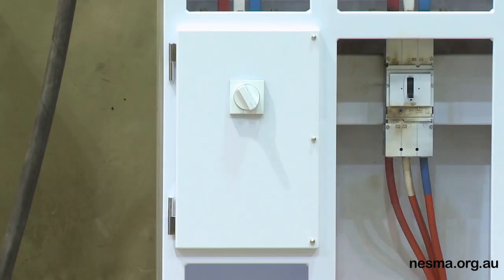What we're going to see now is the next test will be changing that fuse wire short from the load side of the circuit breaker to the line side of the circuit breaker, which means that in this board arrangement there is no protective device between our test supply position and the actual protective device that's in the unit. So the only thing that will be turning the current off is the test station circuit breaker. Probably I think the boys are intending to leave it arc the same duration, 200 milliseconds. So worst case scenario is that we'll have arcing on the line side terminals of that circuit breaker for 200 milliseconds.